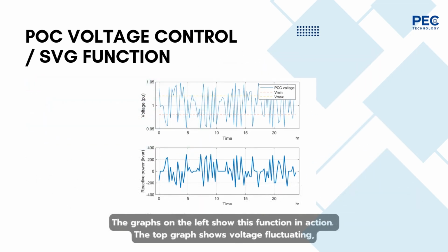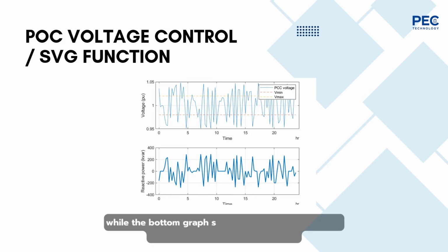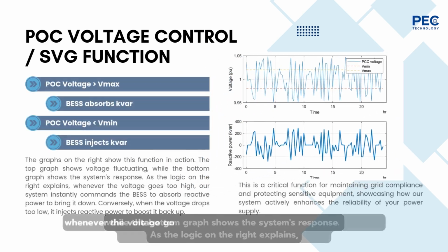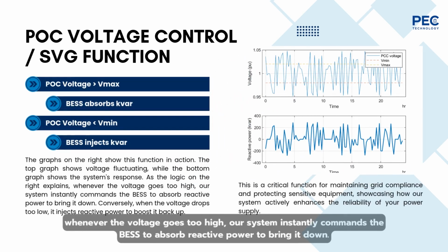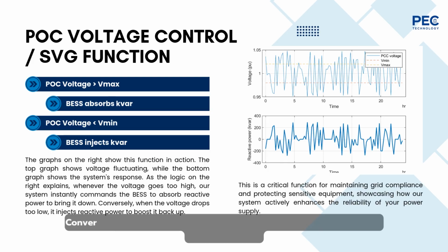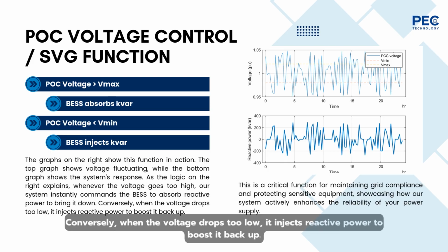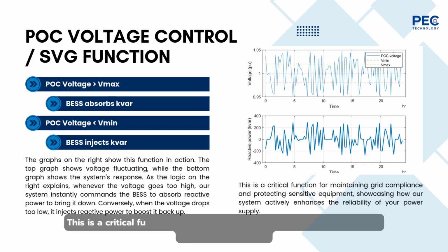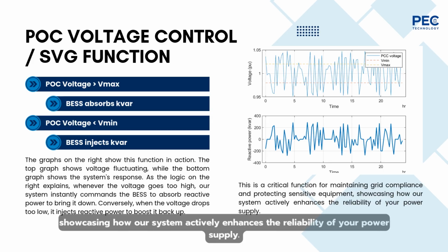The top graph shows voltage fluctuating, while the bottom graph shows the system's response. As the logic on the right explains, whenever the voltage goes too high, our system instantly commands the BESS to absorb reactive power to bring it down. Conversely, when the voltage drops too low, it injects reactive power to boost it back up. This is a critical function for maintaining grid compliance and protecting sensitive equipment, showcasing how our system actively enhances the reliability of your power supply.